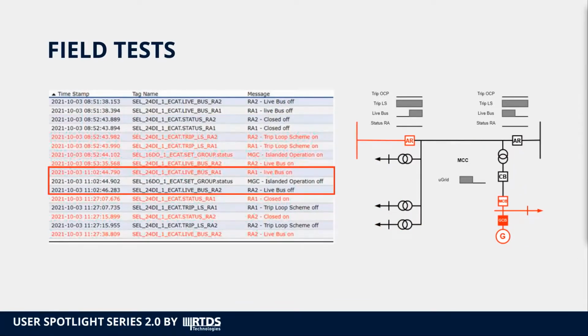After around 1 hour of island operation, the Coppel team returned the energy supply to the microgrid area. Thus, automatic recloser 1, which is in the direction of the substation, detects the voltage at the bus side. And as this is one of the conditions for interrupting the island operation, the Columbary farm returns to operate in parallel with the distribution system grid.